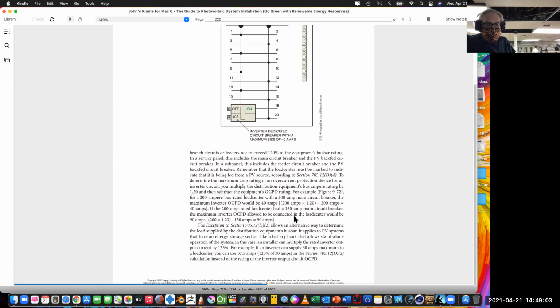When they're talking about this, they're throwing in the concept of having a 20% safety factor. So if you want that 20 or 25% safety factor in there, you've got to reduce this 200 amp breaker. It'd be 150 amp, or connected to a load center would be 90 amps. So you have 200 times 1.20 minus 150 equals 90 amps.